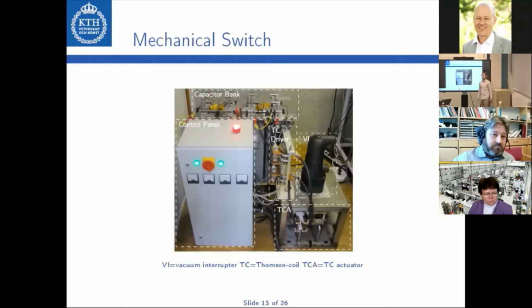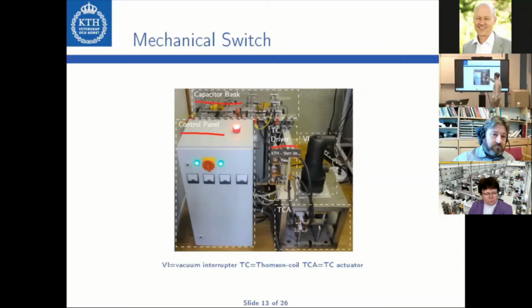As I mentioned to you before, every DCCB needs a mechanical switch. In the laboratory prototype, we used a vacuum interrupter. Here you can see this vacuum interrupter, and it is mounted on top of a Thomson coil actuator. The Thomson coil actuator is an electromagnetic actuator which can rapidly open and close mechanical switches. To operate it, a complex system is needed, consisting of the control panel, the capacitor bank as energy source, and a TC driver.